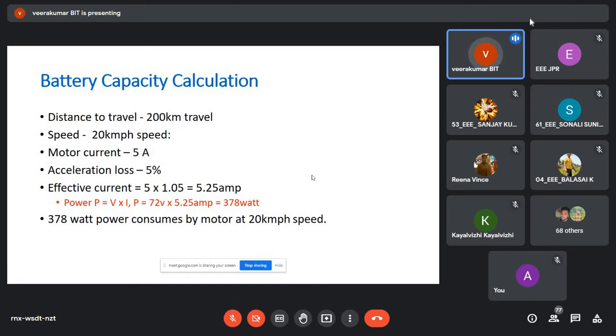And effective current, what do you mean by effective current? We are electrical engineers, we know that because of the absence of back EMF, the motor will draw more current at the initial time. So we multiply by 1.05, so the effective current delivered to the motor, or delivered by the motor, is 5.25.